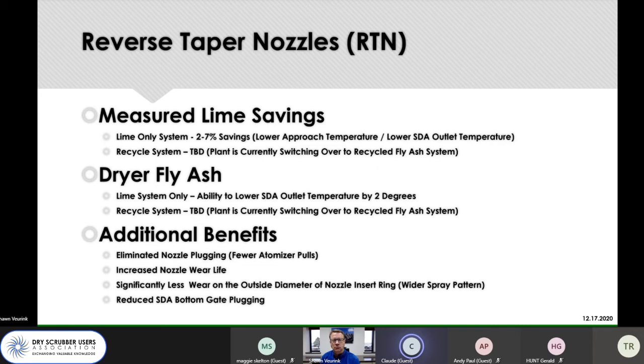With the original design nozzle, where the taper starts larger on the inside and reduces down to a smaller hole on the outside, we would see plugging—if we had a chip or debris, it could enter the nozzle and get stuck in that smaller section. We'd also get buildup of lime slurry solids as it dries out, and we'd end up seeing plugged nozzles during atomizer maintenance. With the reverse taper nozzle, we just haven't seen any of the nozzles being plugged.